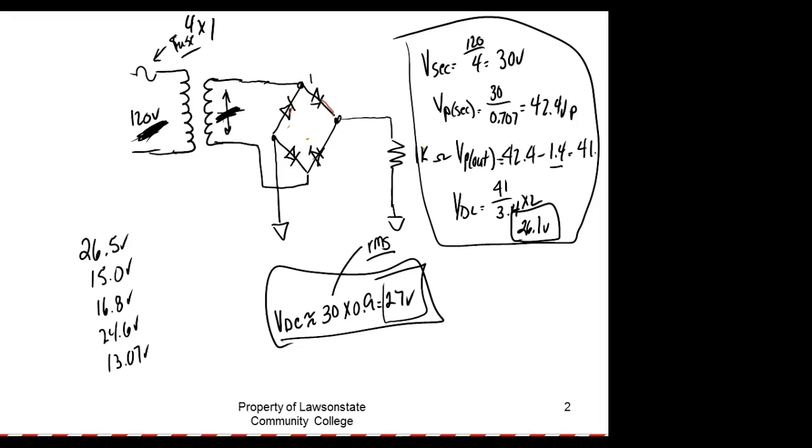But to get the exact answer, the problem we got, guys, is this is not going to be the exact answer, right? You understand? So when we use that 120, under 120 is what the National Electrical Code calls the nominal voltage. And then they say, well, legally it could be 120 plus or minus 10%. So legally it could be around 100 volts, but it could be up here. And according to the National Electrical Code, that would still be legal for what Alabama Power is giving you.